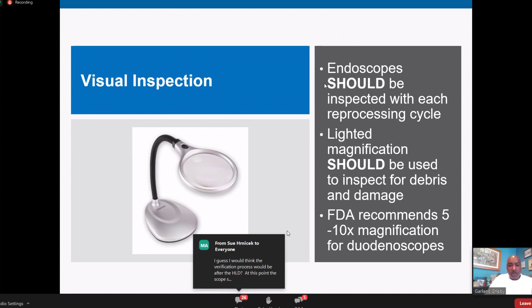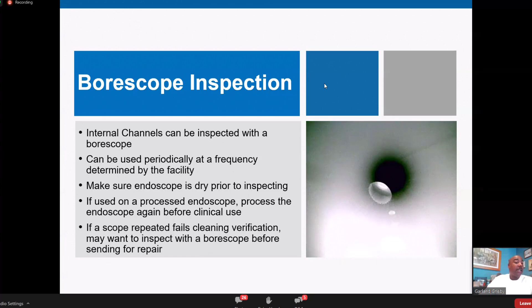Borescope inspection. Some folks have had a borescope. Some folks have heard about borescopes. We discussed this as far as its purpose, checking the internal channels. There are many different sizes out there that you can use for the different scopes that you have. You can use it periodically. You can definitely use it on your high-risk scopes. You want to make sure that the scope is dry prior to inspecting, because when you drive that borescope down that lumen, you will see all the water droplets that are there. It's actually a good way to test how your drying is in your facility. Are your scopes dry when they're hung? Are they dry after 4 days of being in a scope cabinet?